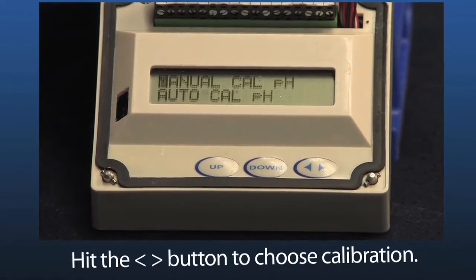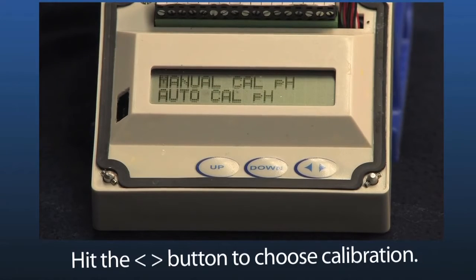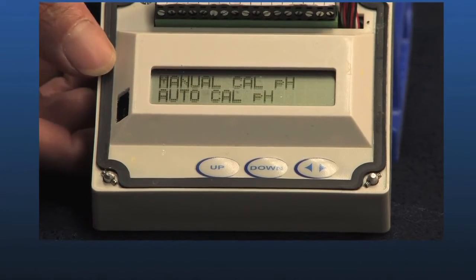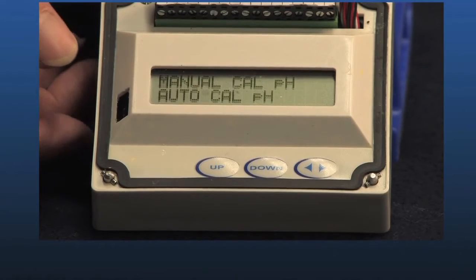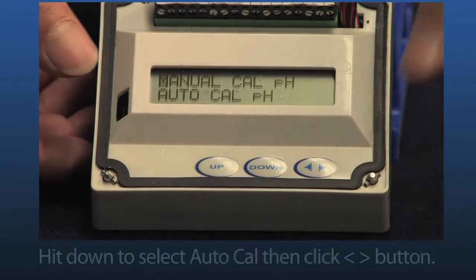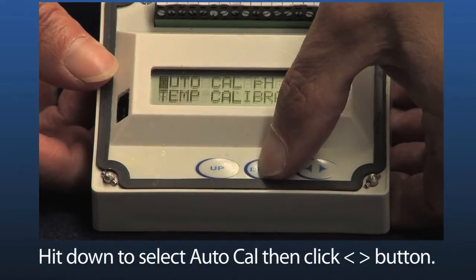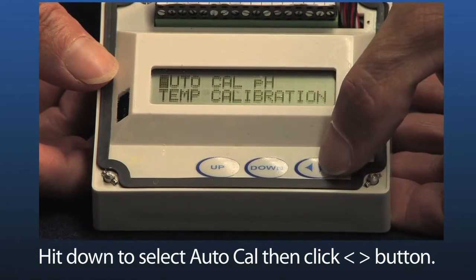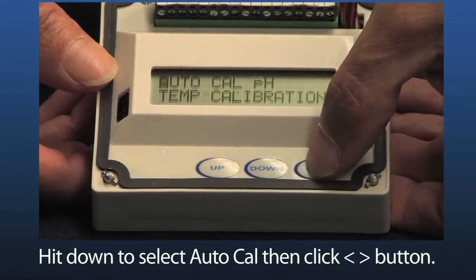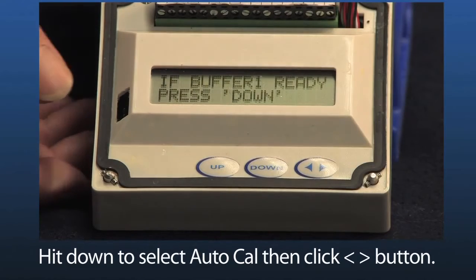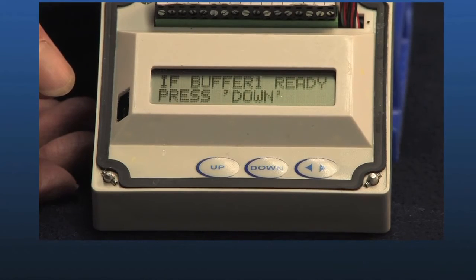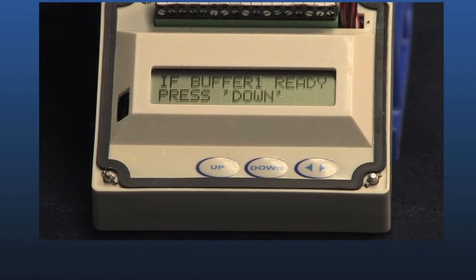Now I'm given a choice between manual cal and auto cal, and I really only ever need to use manual cal if I have a really sick probe. For all other reasons, I always choose auto cal. Again, I press the left right button to choose it. And now it says, if buffer 1 is ready, press down.